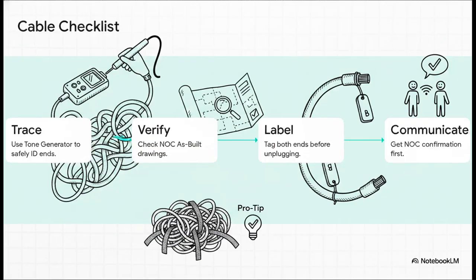To prevent that kind of catastrophe, you must strictly follow a 4-step verification checklist before you even think about touching anything. First, you start by tracing the cable using a tone generator, which is often called a fox and hound, to safely identify where it goes without having to unplug it. Then you verify it against the site's map. If it's not on the map, you stop. If you absolutely must disconnect it, you label both ends, and most importantly, you communicate with a NOC to get their explicit approval. And as a quick pro tip, always leave the site better than you found it. Use Velcro straps to organize the cable spaghetti. True professionalism is visible to the next person who walks through that door.